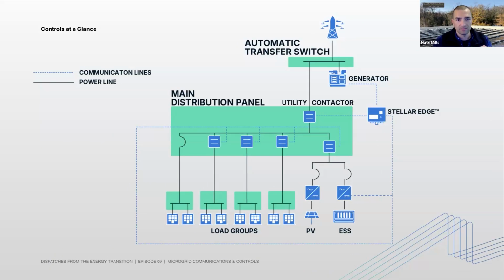The blue boxes, aside from the generator, are what we bring when we bring a microgrid to life. So we will add some solar. That's the PV, bottom right. That's the ESS, so we'll bring the battery as well. And we'll bring a control system, that's the Stellar Edge, and then some version of load shedding often. And that's what these contactors are intended to show, except for one, and that's the utility contactor at the top of the main distribution panel.